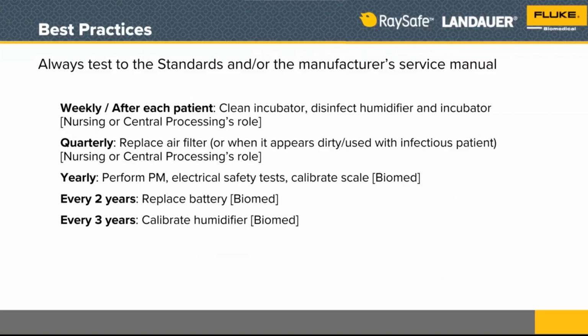So there's both nursing and central processing roles here in terms of testing infant incubators. Weekly and after each patient use, the nursing department has some things that they need to do, cleaning the infant incubator, disinfecting humidifiers and things like that. Quarterly, the nursing department and or central processing also need to replace air filters, or when it appears dirty, they need to be replaced or cleaned. And there are other things that need to be looked at too, including gaskets and so forth that help prevent temperature loss, thermal loss from inside the chamber.